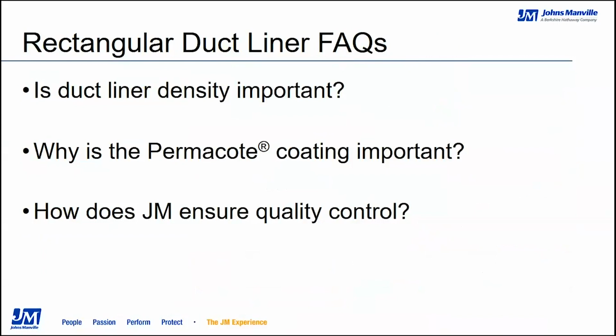So in 1986, the insulation manufacturers and ASTM recognized that all duct liners were not the same, and they attempted to rectify this by approving a new duct liner selection criteria, ASTM C1071, the standard specification for fiberglass duct lining insulation. When this new standard was established back in 1986, density was actually removed and no longer listed as a requirement.